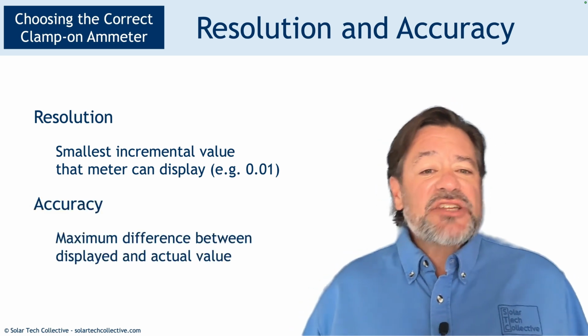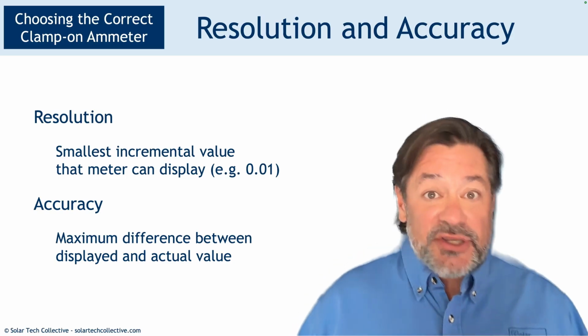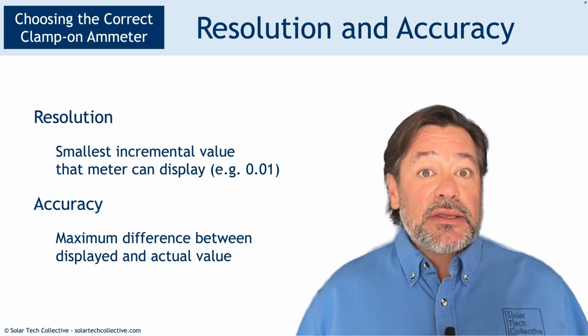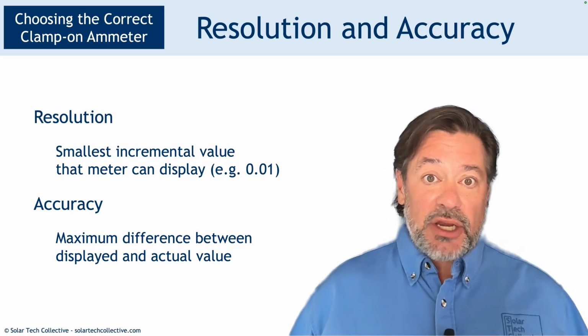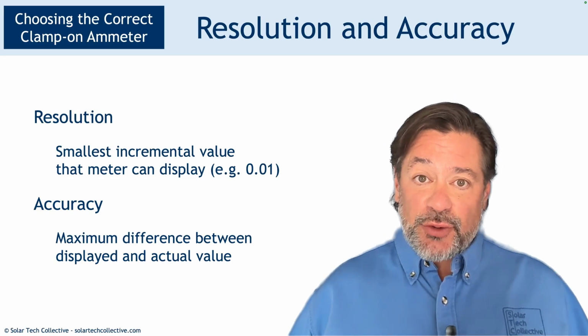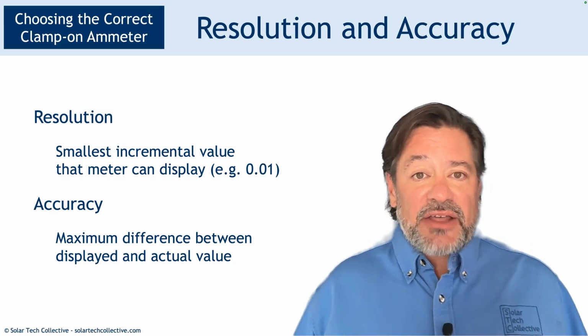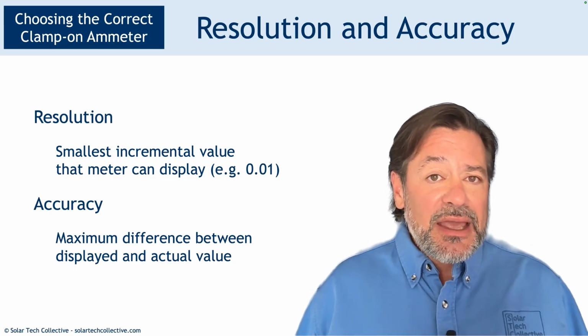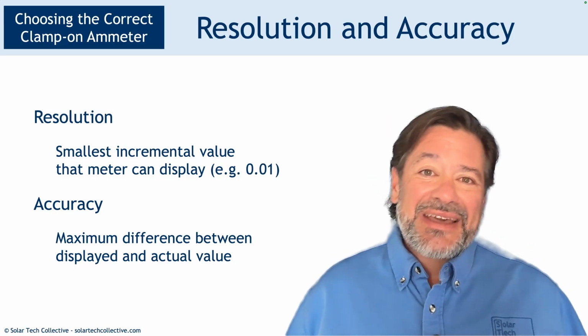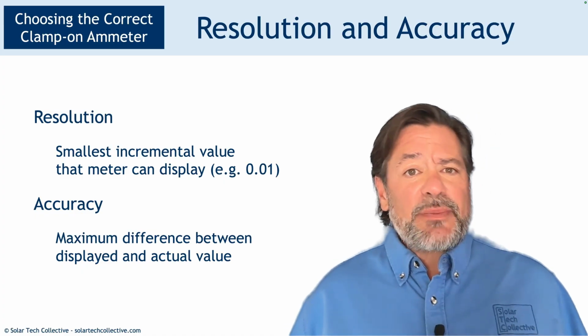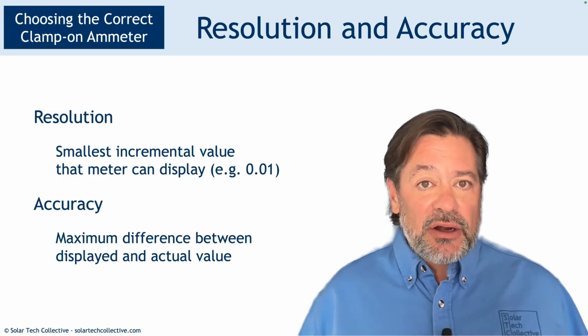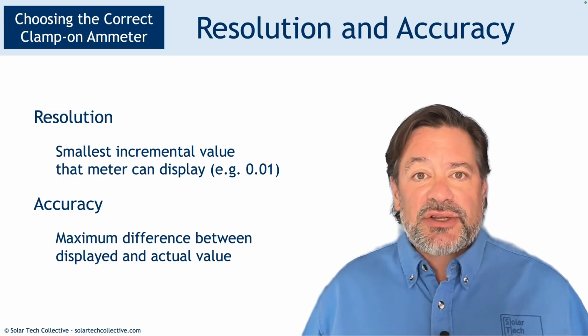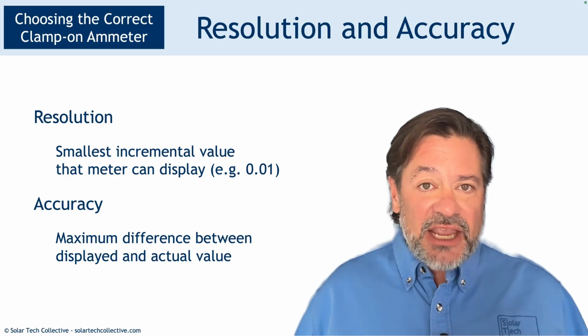Accuracy is the maximum difference between what the meter says and what the real value is. Higher quality meters are going to be more accurate. Meters can drift. They may need to be calibrated. We'll follow the manufacturer's instructions for that. And different manufacturers are going to give you these values in different ways, which can make it difficult sometimes to truly compare. What we'd really like would just be a percentage. Is it 2%, 5% accurate, whatever that number may be?